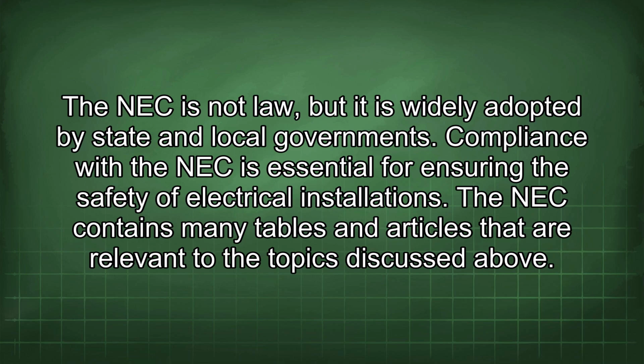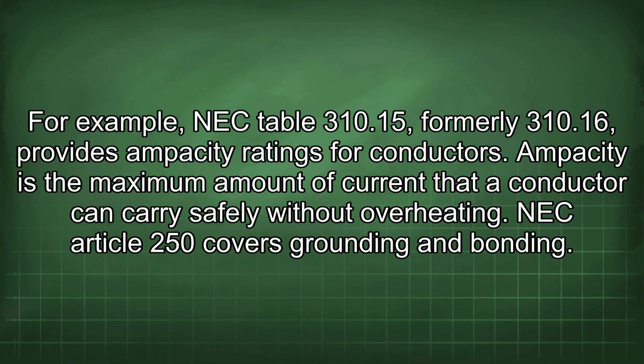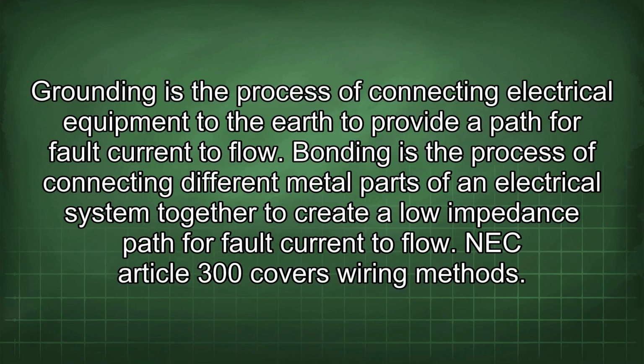The NEC contains many tables and articles that are relevant to the topics discussed above. For example, NEC Table 310.15, formerly 310.16, provides ampacity ratings for conductors. Ampacity is the maximum amount of current that a conductor can carry safely without overheating. NEC Article 250 covers grounding and bonding. Grounding is the process of connecting electrical equipment to the earth to provide a path for fault current to flow. Bonding is the process of connecting different metal parts of an electrical system together to create a low impedance path for fault current to flow.